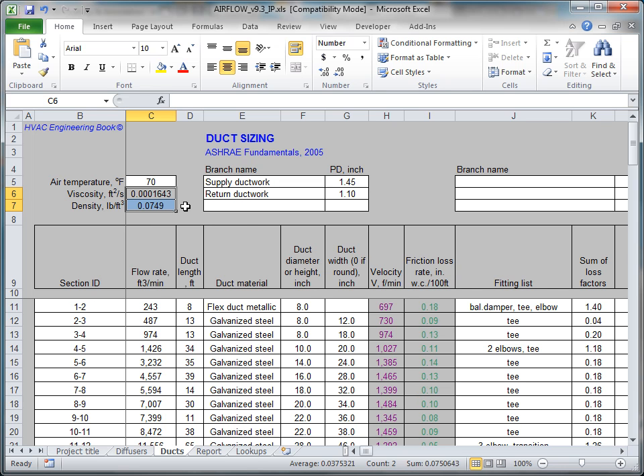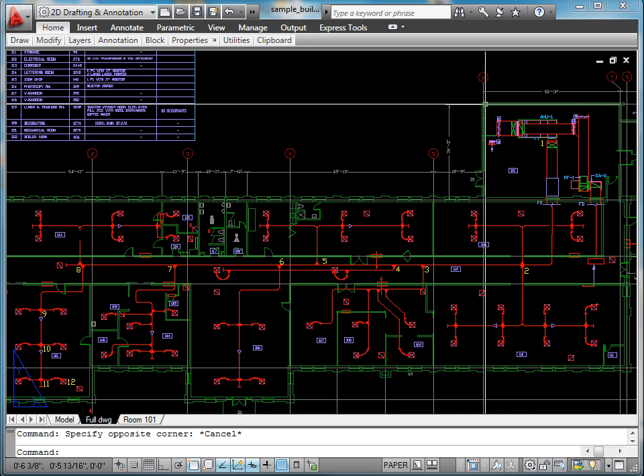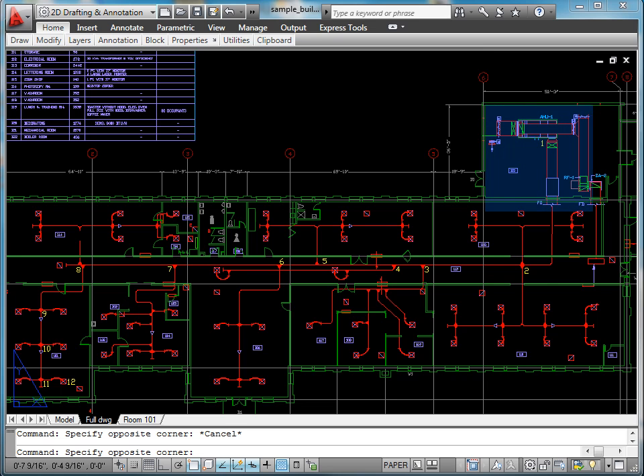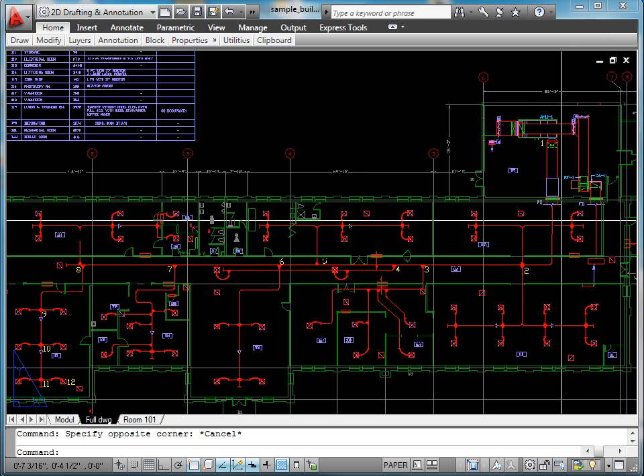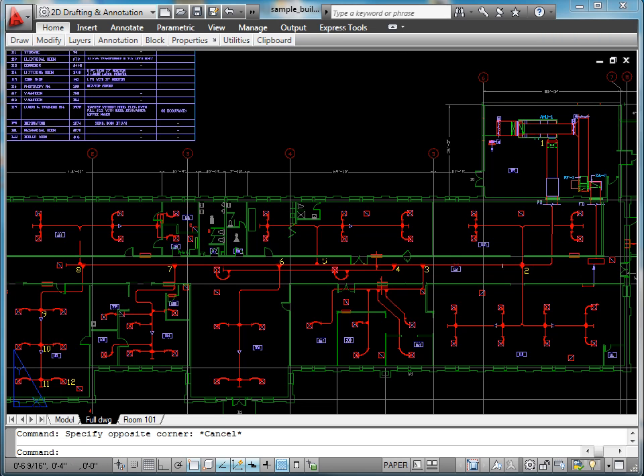Now, size the longest and most loaded duct work branch to obtain the static pressure that the air handling unit supply fan will need to generate. You will repeat the same procedure for all duct paths. In our sample building, the most loaded duct path starts at the air handler and ends in space 101.